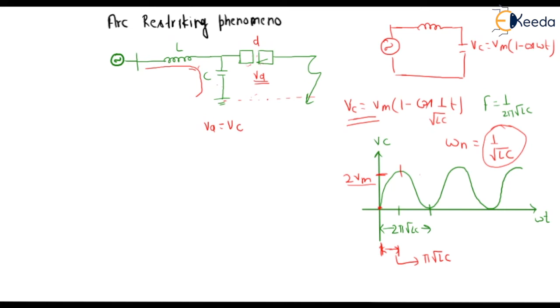Again, if the dielectric stress is greater than the dielectric strength of the material, then the arc will restrike again. So basically the arc will strike again. That is why this phenomenon is called the restriking phenomenon. So this is the whole restriking phenomenon. This 2 Vm is the maximum value of the restriking voltage, and to reach that maximum, it will take pi root LC time. So this is the diagram.